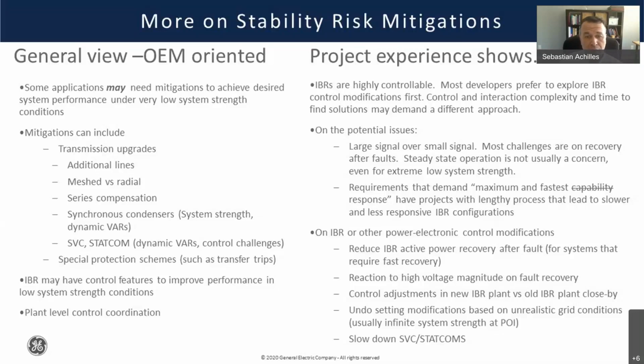In terms of the specifics of the inverter-based resources or other electronic control modifications, slowing down the active power after a fault is relatively common. It's related to the point I mentioned before. Slowing down the recovery of active power allows the reactive power controls to ensure that there's enough reactive power to transfer the generation of the different sources during a contingency condition.